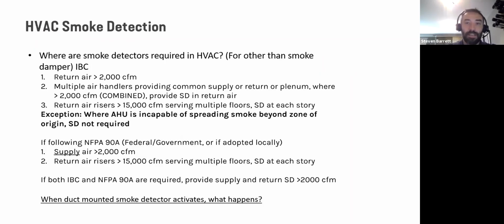So that's the segue into this next section. When are smoke detectors required in HVAC, other than what we just talked about for shutting the dampers? Well, there's three conditions. If your return air system exceeds 2000 CFM, provide a smoke detector. If you have multiple air handlers, the common supply or return, where 2000 CFM combined, provide a smoke detector in that return air. And then in large systems exceeding 15,000 CFM, serving multiple floors, provide the smoke detectors at each story. One important exception, though, is that if the air handling unit is incapable of spreading smoke beyond the zone of origin, then the smoke detector is not required.